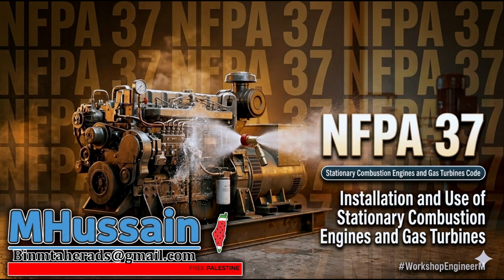The louver trap. This is where the electrical design ruins the mechanical design, right? Exactly. These motorized louvers need power to open. When utility power fails, designers often wire the louvers directly to the generator's start circuit. Because the generator is the only thing making power. Logically, yes. But what if the actuator gets stuck? What if ice freezes the louver shut on the outside wall? Oh, man. So the engine starts, but the louver stays closed.